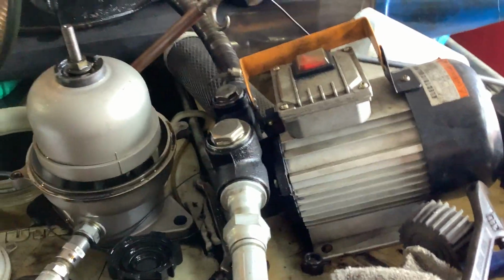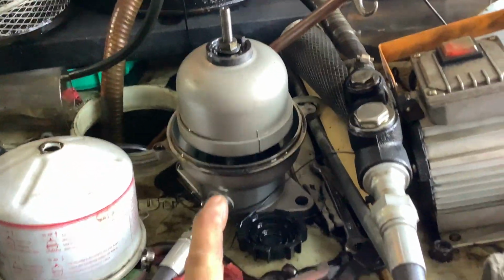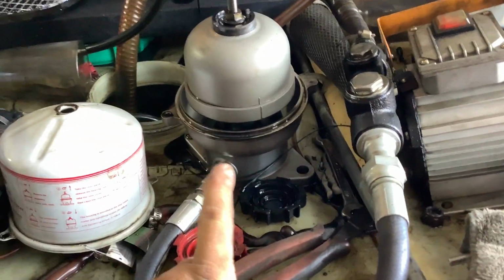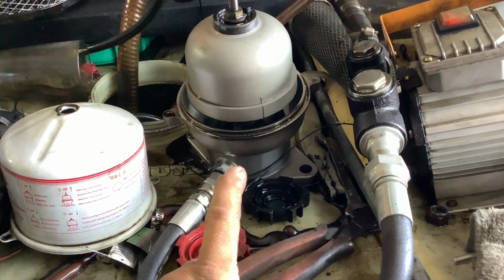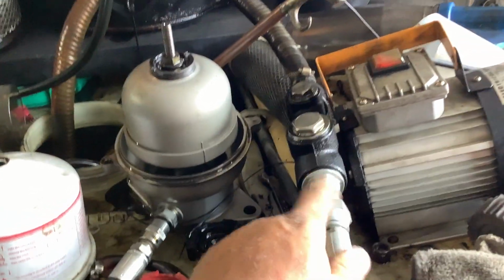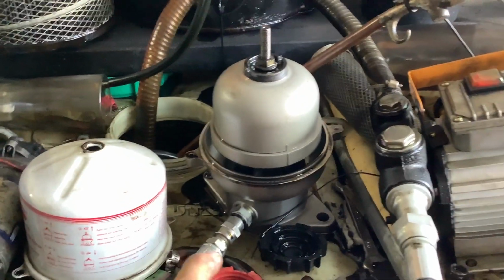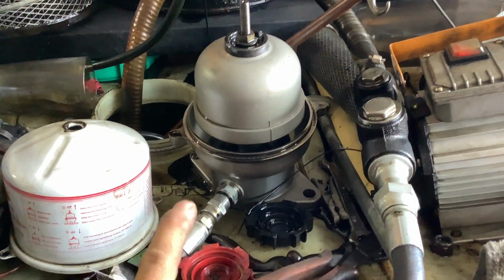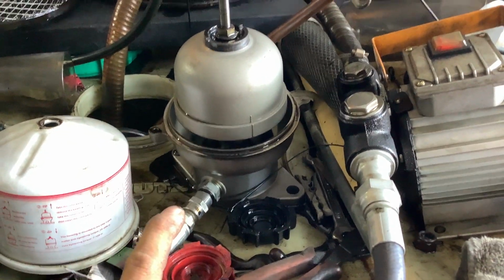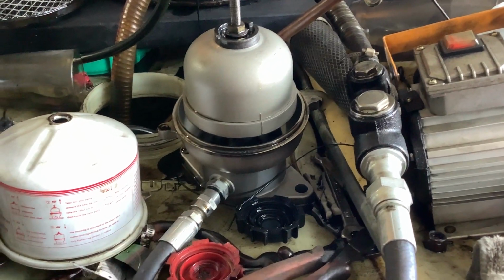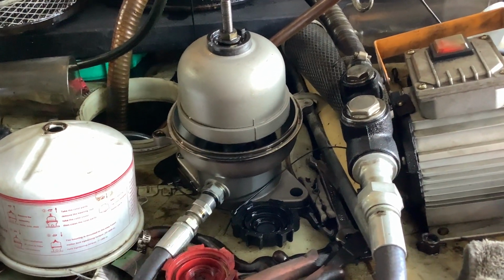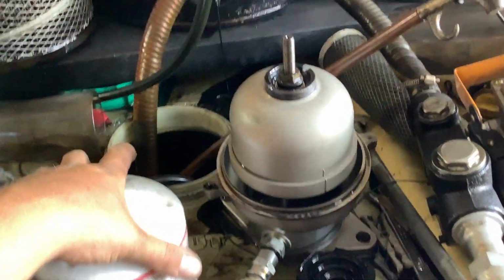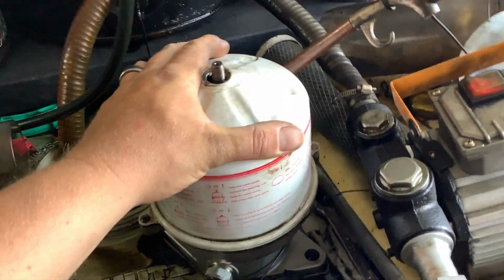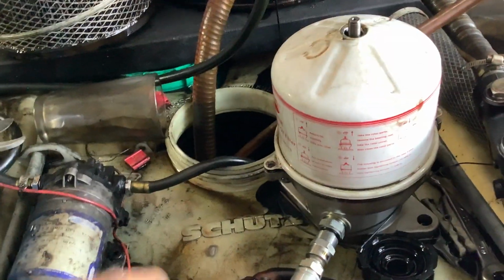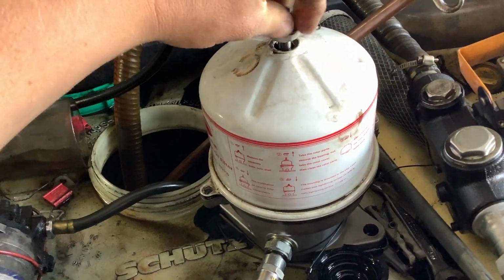This does around 14 litres a minute at 85 psi. I think I've got about 60 psi, judging by the sound the relief valve makes when the oil's thick, which gives me around 10 to 12 litres a minute. So 10 litres a minute turns the tote over in 100 minutes, which is just under 2 hours - so every 2 hours, conservatively, you turn the entire tote over.